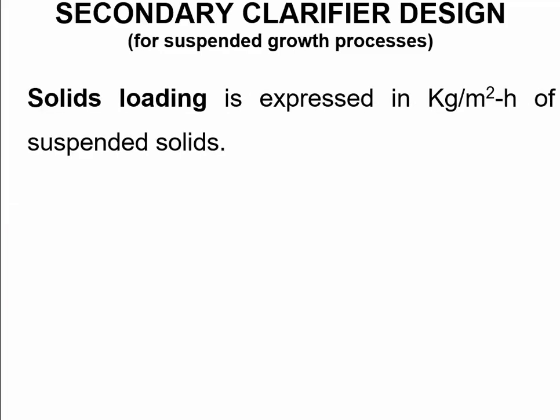Solids loading rate is expressed in terms of kilograms of solids applied to the unit area of a secondary clarifier per unit time. So kilograms of solids per hour per square meter of the secondary clarifier area.